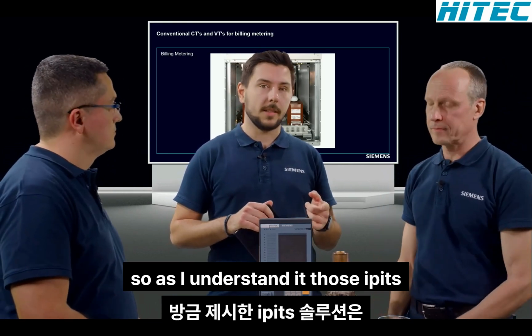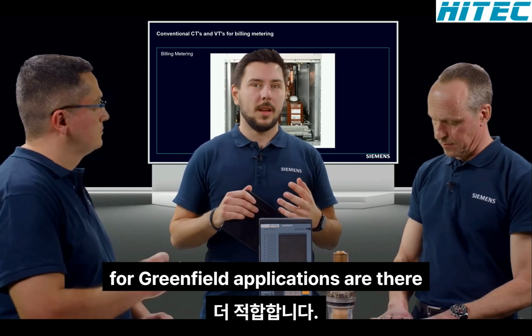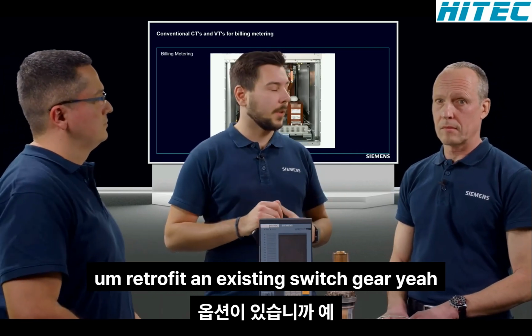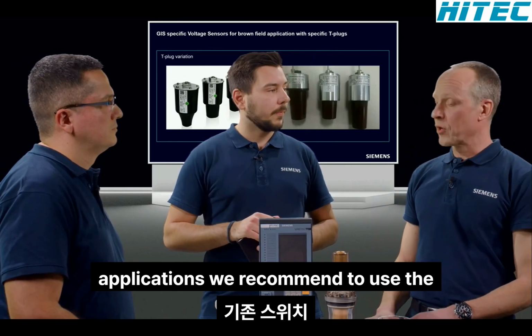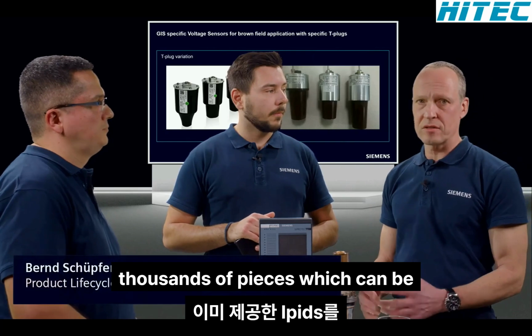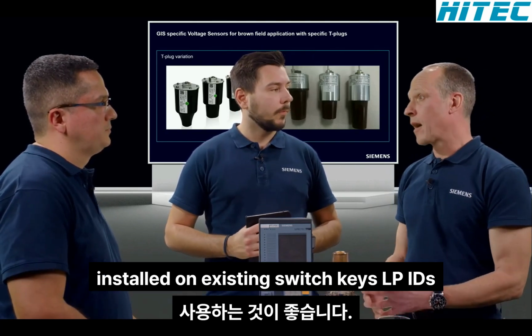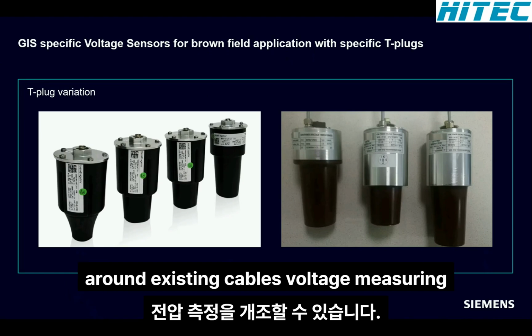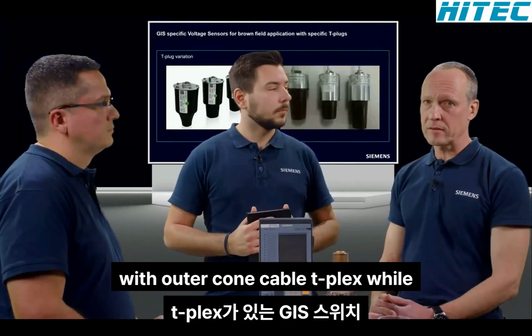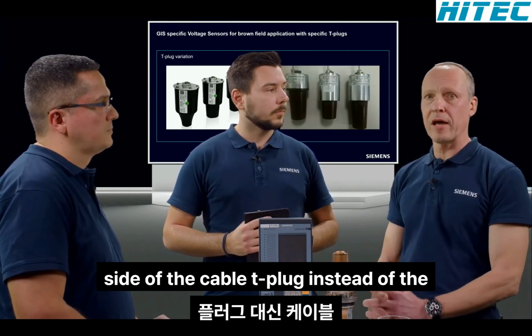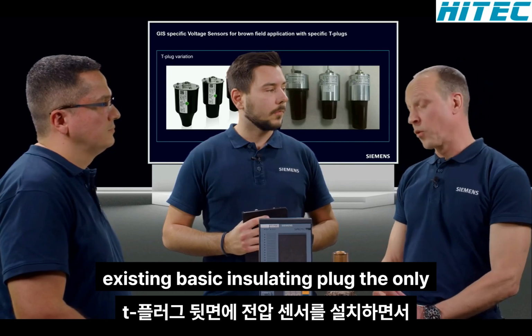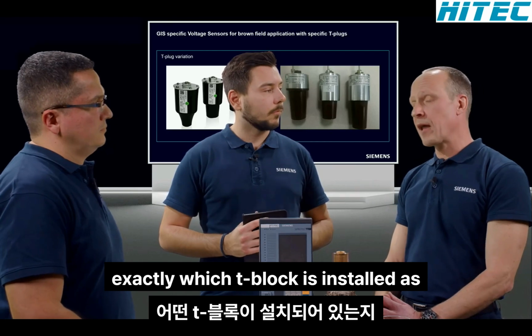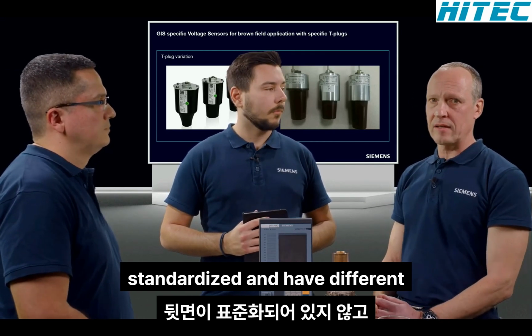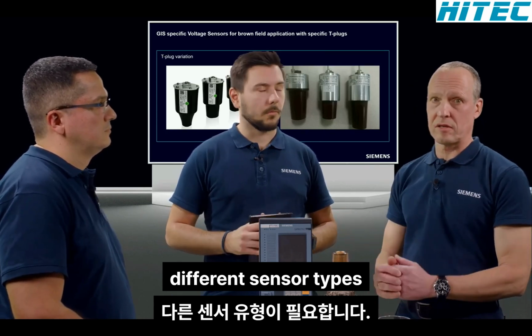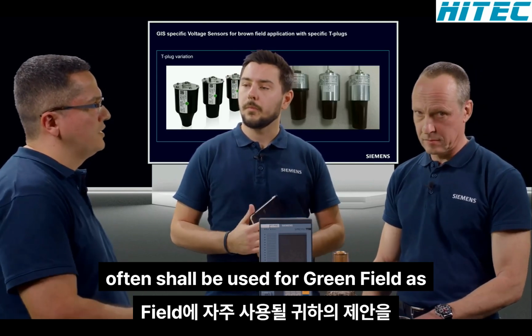So as I understand it, those LPIT solutions you just presented are more for greenfield applications. Are there any options to retrofit an existing switchgear? Yes, there are. For brownfield applications, we recommend to use the LPITs we have already delivered in thousands of pieces, which can be installed on existing switchgears. LPITs for current measuring in a split core design can be installed very easily around existing cables. Voltage measuring can be retrofitted on GIS switchgear with outer cone cable T-plugs, by installing a voltage sensor in the backside of the cable T-plug instead of the existing basic insulating plug. The only challenge we face here is to know exactly which T-plug is installed, as the backsides of them are not standardized and have different dimensions, which therefore require different sensor types. So Bernd, what's your suggestion here? Which of them shall be used for greenfield as well as for brownfield applications?